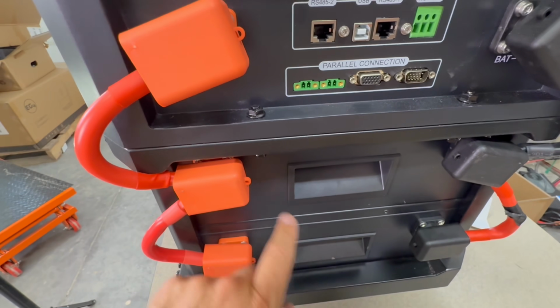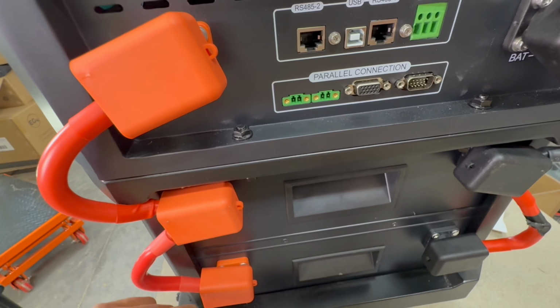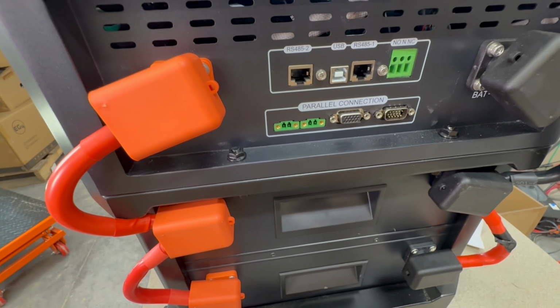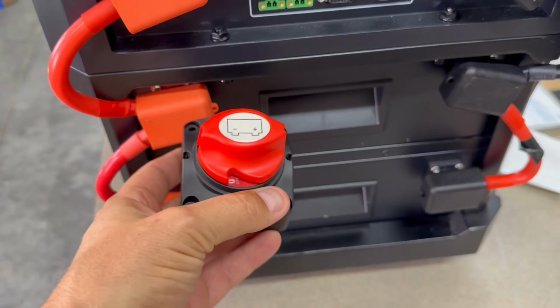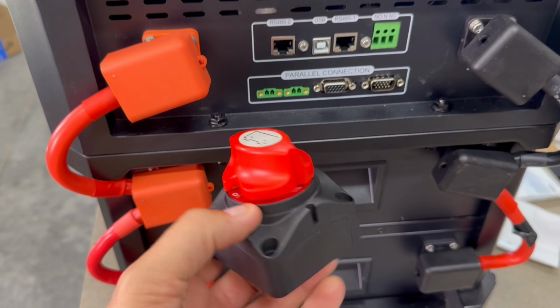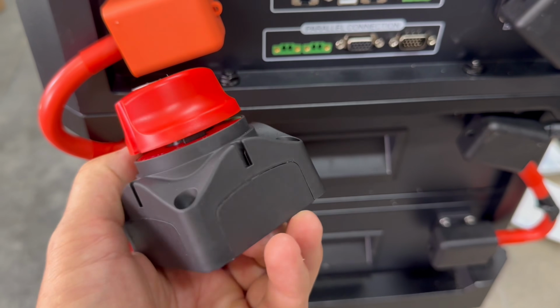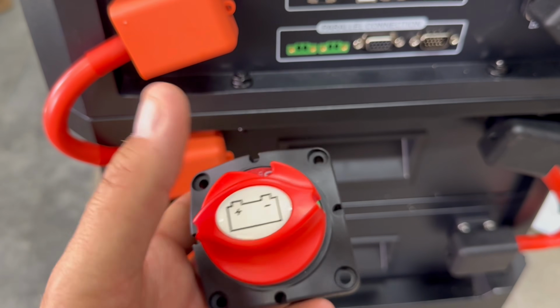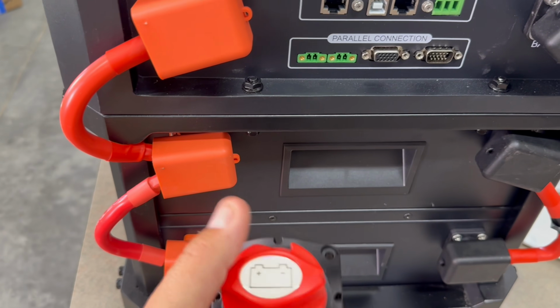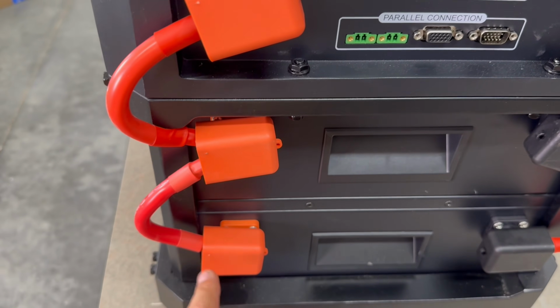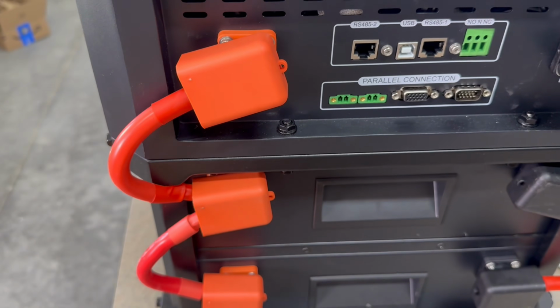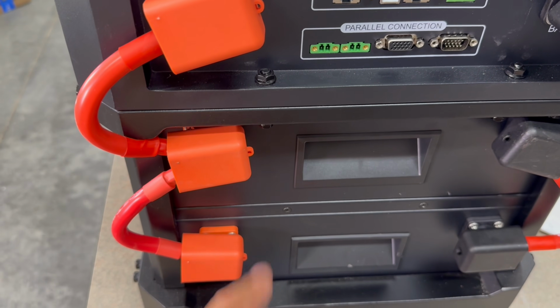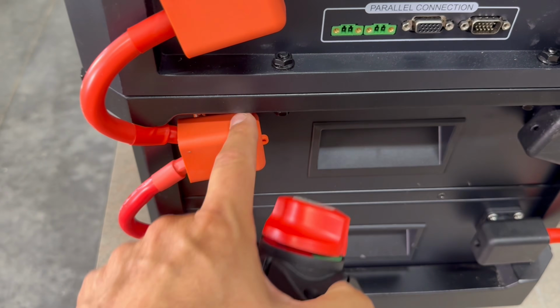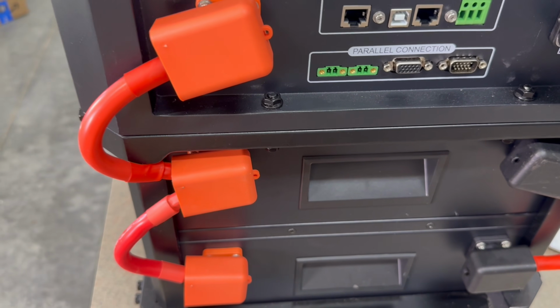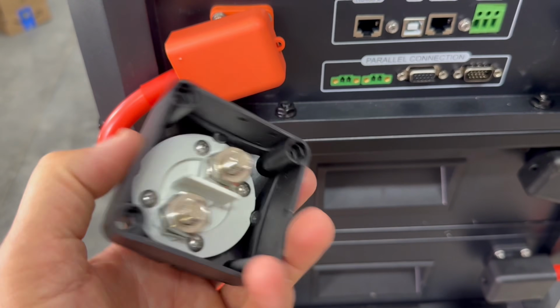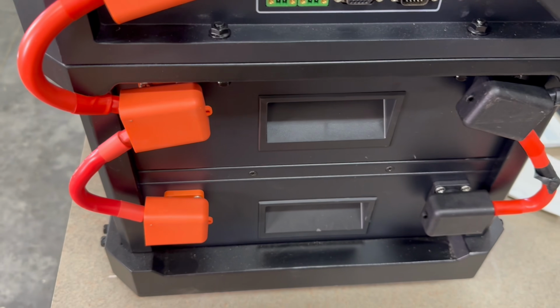So they don't have any breaker, any overcurrent protection for this, but they did provide a means of disconnect. I'll show you that here in just a second. This is what they're providing as a means of disconnect between the batteries and inverter. Granted, there's no overcurrent protection, but this is a way to shut the inverter off from the batteries, disconnect them completely. Right now, even with these off, and I actually have the switch off, it's going to have a slow draw from these batteries. Plus if you install these directly you're going to get a spark, and if you have this off and install it, at least you're not going to see the spark on the outside. But yeah, this is what they supplied.